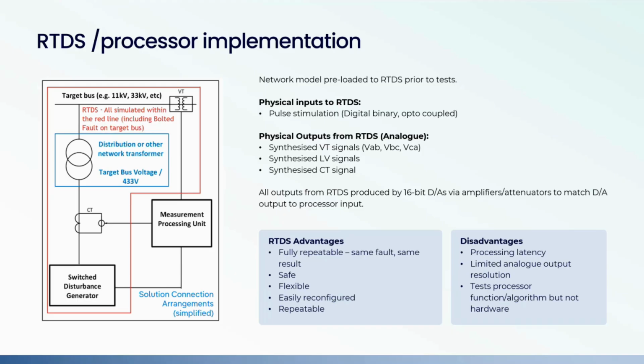The real-time digital simulator is a very good place to start, really, because it's got some major plus points. It's safe, there's no high voltage involved, there's no physical risk, we don't need outages. It's flexible. We can change things around. We can test at different voltages. We can change the characteristics of the disturbances, and it's repeatable.